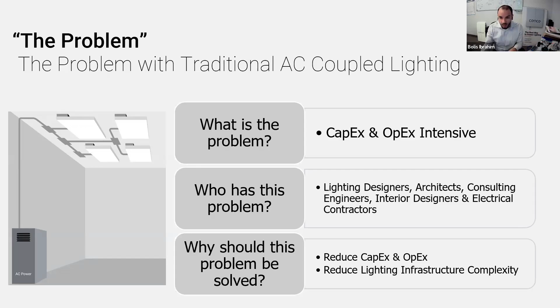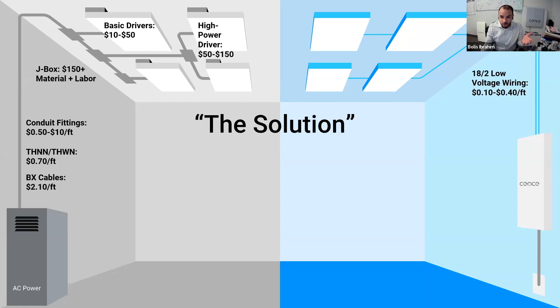The solution is to remove mechanical protection - remove BX, remove line voltage cable, remove conduit fittings. That's a lot of labor, junction boxes, labor costs everywhere - and drivers - then replace all of that with just low voltage wiring and driverless fixtures. Oftentimes manufacturers provide fixtures at lower cost because they don't have a driver. There are over 1,200 UL and ETL listings of low voltage fixtures, and I can share that list with anyone who's interested.